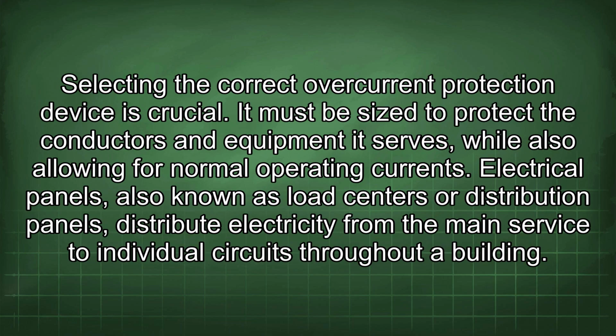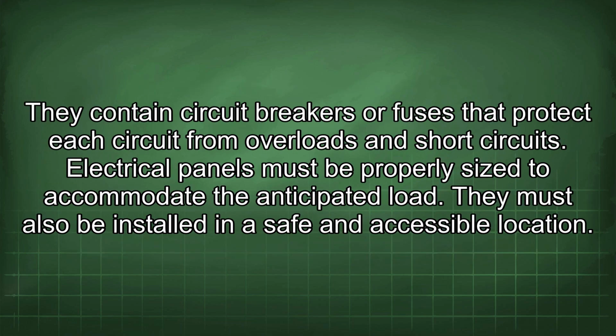Selecting the correct overcurrent protection device is crucial. It must be sized to protect the conductors and equipment it serves, while also allowing for normal operation currents. The electrical panels, also known as load centers or distribution panels, distribute electricity from the main service to individual circuits throughout a building. They contain circuit breakers or fuses that protect each circuit from overloads and short circuits.